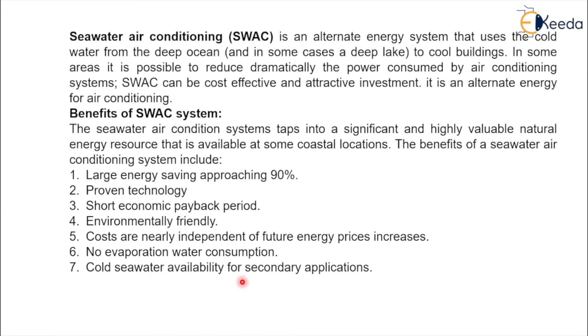Short economic payback period. It means in a very short period of time, we can get back whatever investment is made. It is environmentally friendly because there is no refrigerant. Costs are nearly independent of future energy price increases. In a vapor compression refrigeration system, we use electricity to run the compressor and other equipment, so if electricity charges increase, the air conditioning charges will also increase. But in a seawater air conditioning system it is nearly independent of future energy prices. There is no evaporation water consumption. Cold seawater is also available for secondary applications. The seawater that goes for the air conditioning purpose can afterwards be used in some other applications.